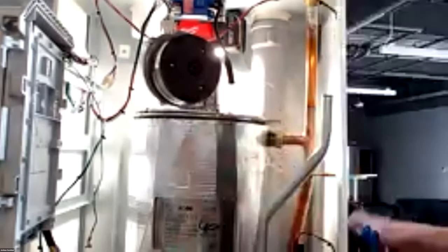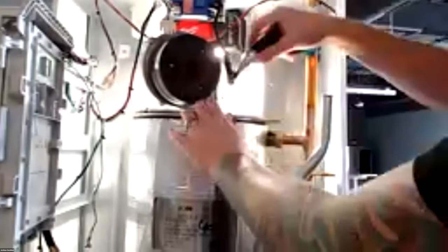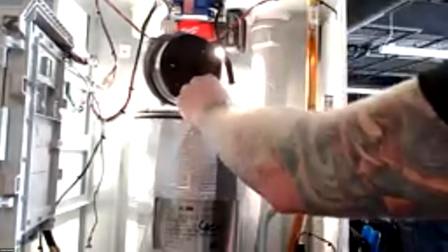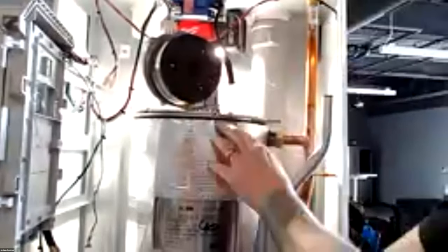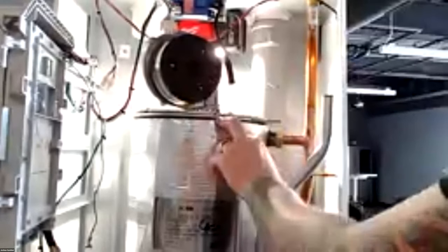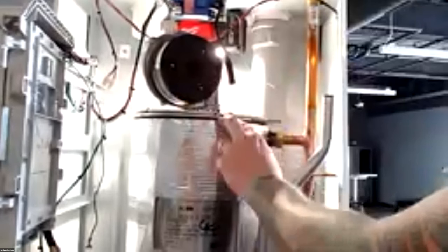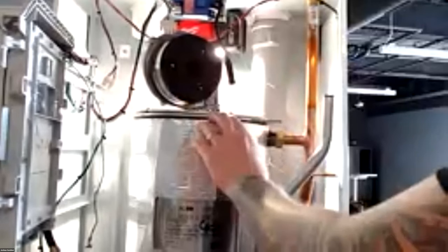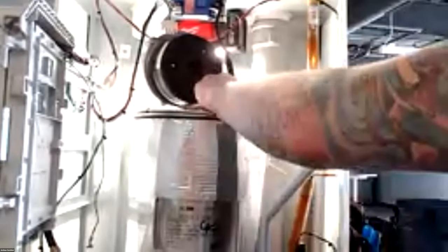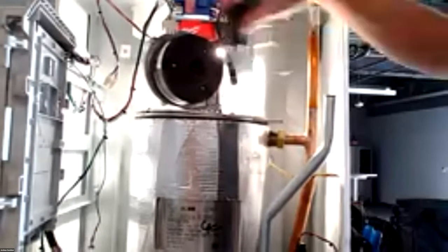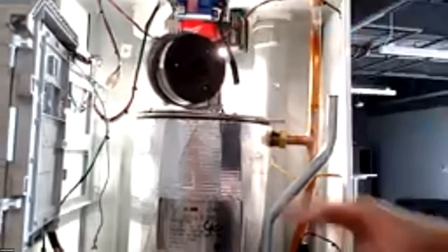These work really well. You don't want to over torque these. So a couple things is if we over torque these and really wrench them down, you could break those studs. And these ones, I have not seen that yet. You'd have to get it really hard, but you could flatten out and smush out this gasket if you really torque it down too much. And then that could be a potential leak on the heat exchanger plate. So I believe off the top of my head, I think it's 40 pounds or 35 pounds torque. So you'll just torque those down and then just do that in an offset.